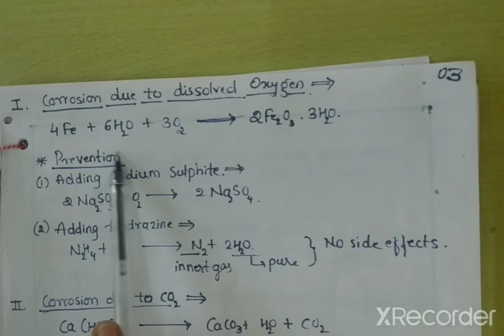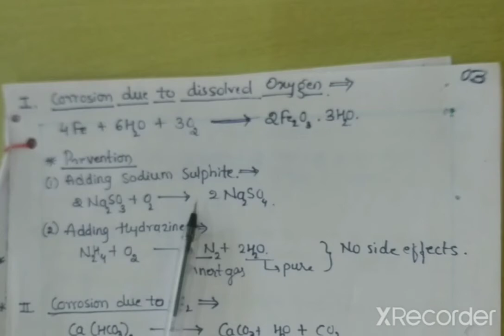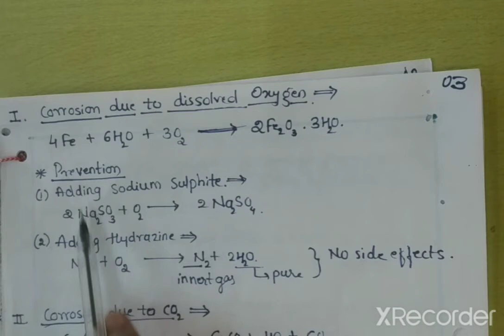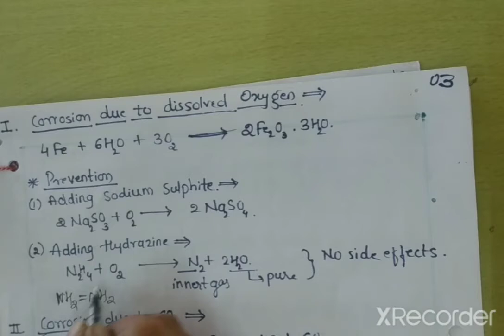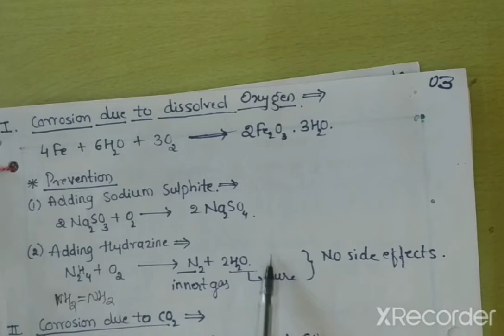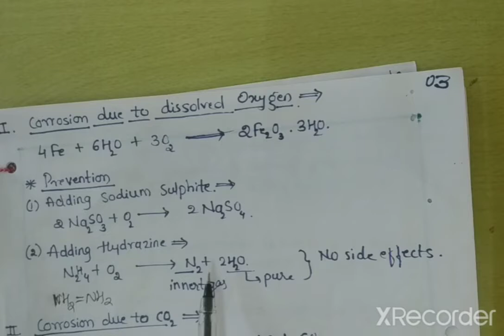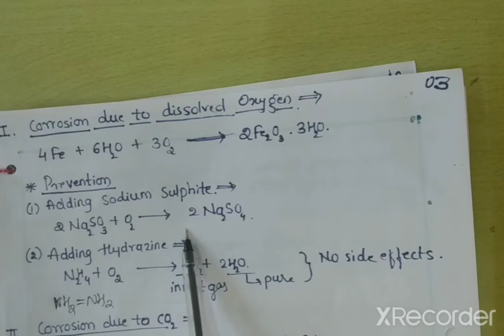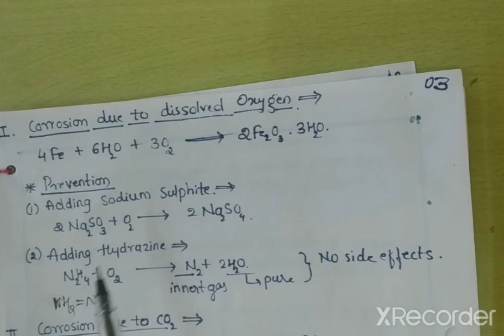How to prevent this? In order to prevent it, you can add sodium sulfite, Na2SO3, which in the presence of oxygen forms sodium sulfate, Na2SO4. The second prevention method is adding hydrazine, N2H4. Hydrazine in the presence of oxygen gives an inert gas: nitrogen gas is liberated along with the formation of pure water. This reaction has no side effects, so you can prefer it over the sodium sulfite reaction. So this is about the prevention of boiler corrosion.